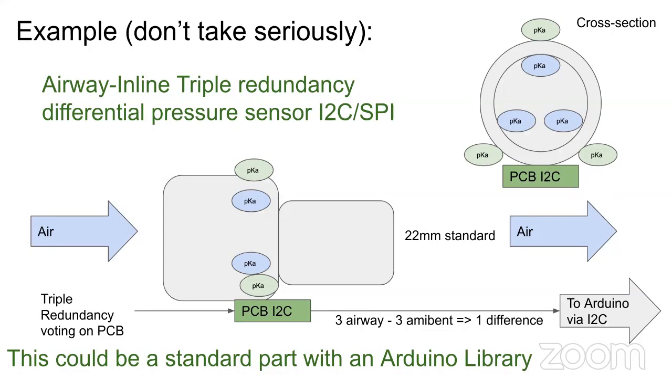And I buy a lot of things from, let's say, Adafruit or whatever. I've got a flow sensor from Adafruit right here. If I had this, I think a lot of ventilator projects could benefit from it.